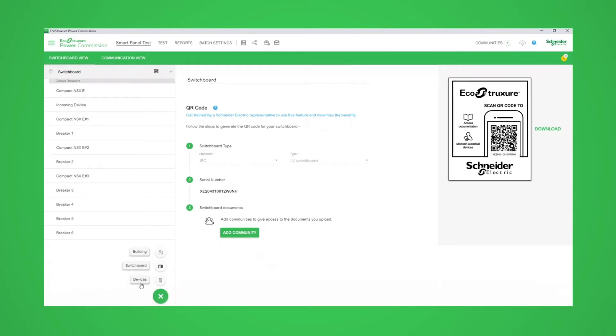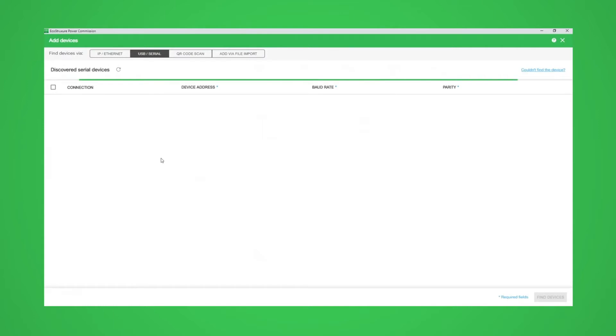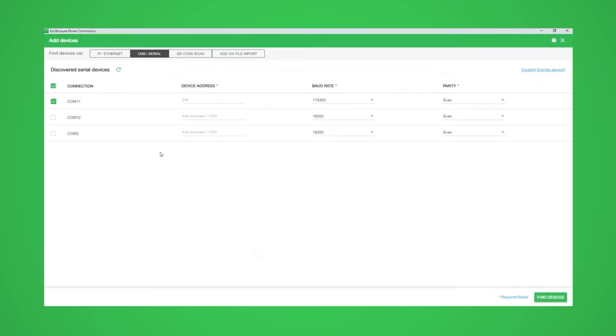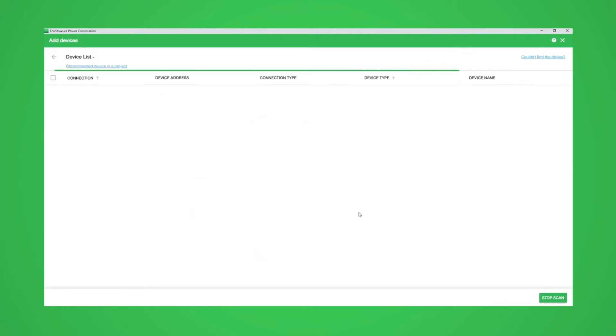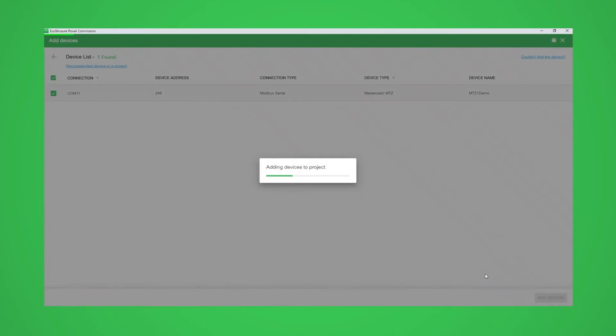We start by adding an MTZ device. This needs to be direct connected via USB into the front of the trip unit. You may need to check your Windows device settings to confirm which COM port is being used. Once selected, click on Find Devices. This will scan and show which devices have been found. Click on Add Devices to add the MTZ to the project.